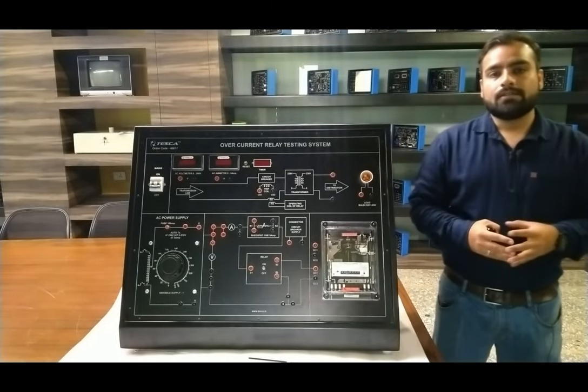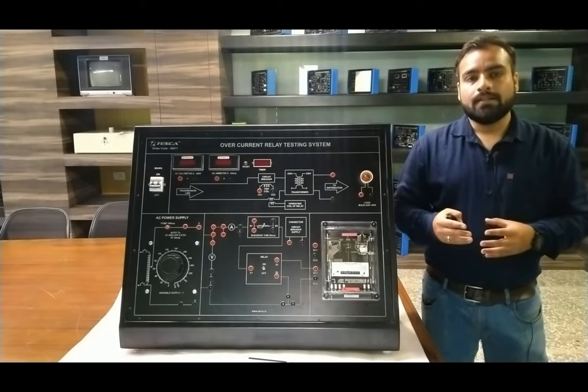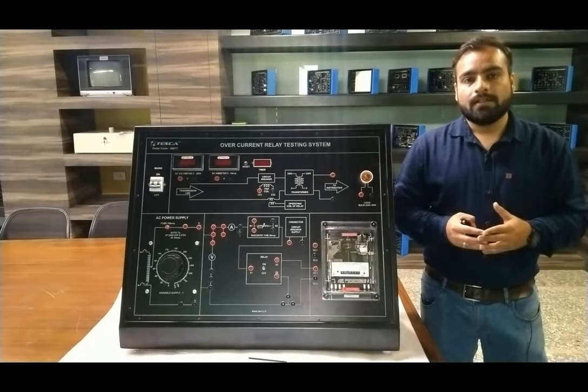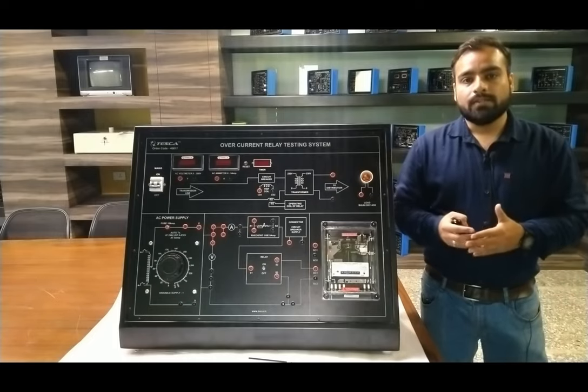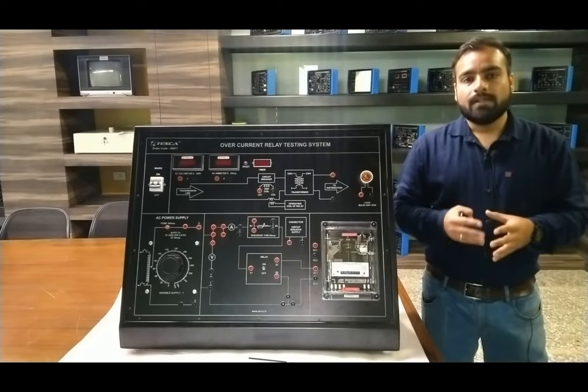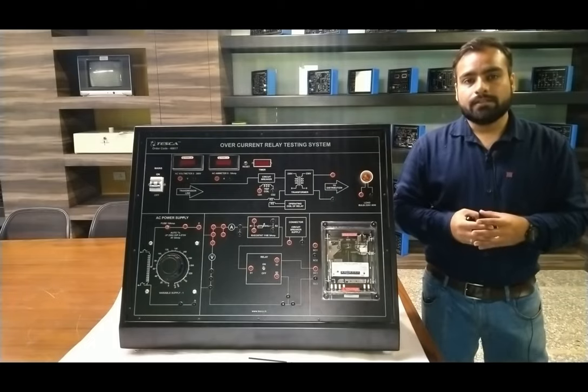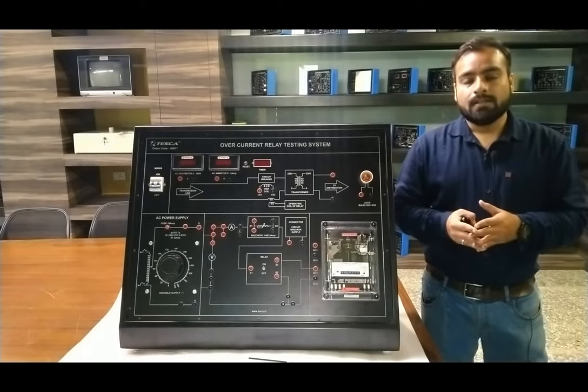In short, when the current value in the overcurrent condition is increasing continuously, the tripping time of the relay will decrease inversely. So when the current value is very high, the tripping time is very low, providing protection as per the time dependency, so that the distribution system will be isolated properly, and if the current is due to any surge or false conditions or any load increment, it will be maintained as per the tripping value.